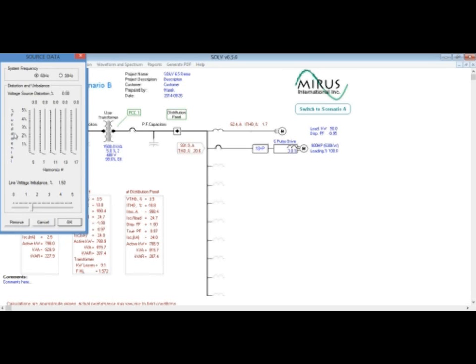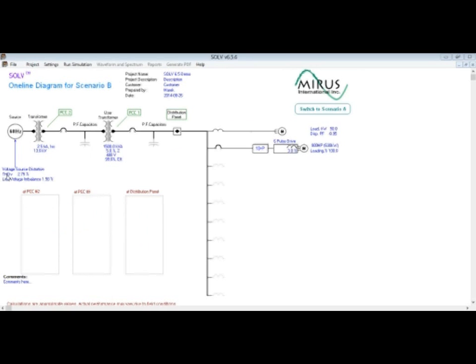the voltage background distortion. We have allowed for 5 major harmonic components in the source voltage distortion. By sliding the indicators, I can set the level of each harmonic in the background. So let's set some numbers here for all 5 harmonics, and I'm setting up 2.75% of voltage distortion, which is very common in many industrial systems. Now I click OK, and we notice 2.75% voltage distortion together with the imbalance, and I run the simulation.